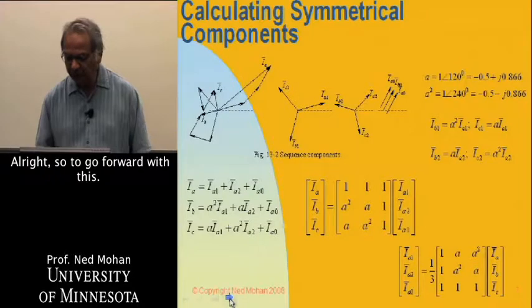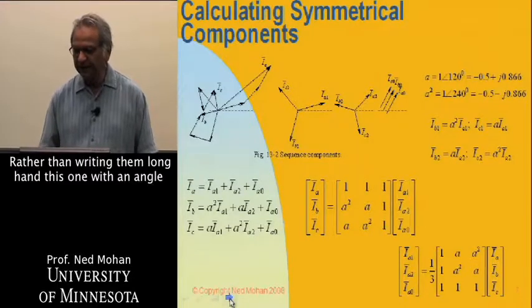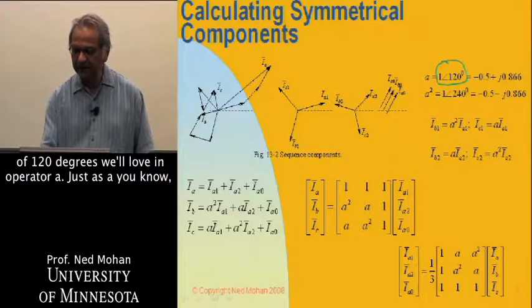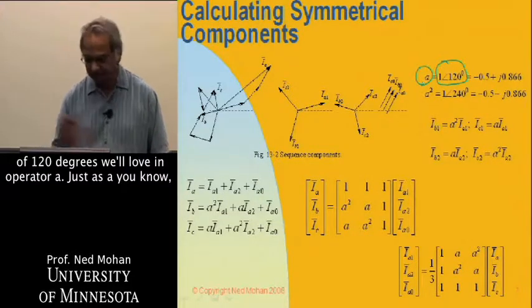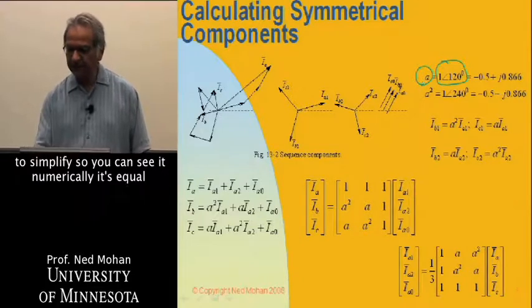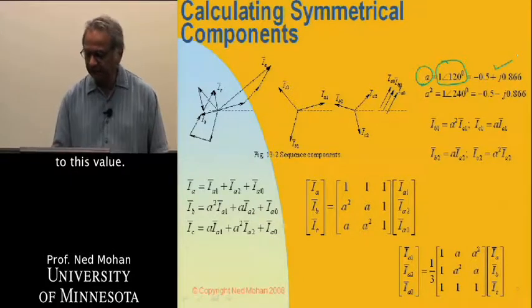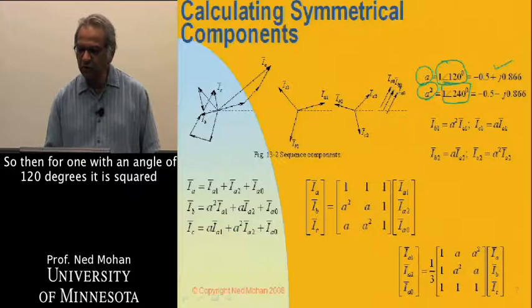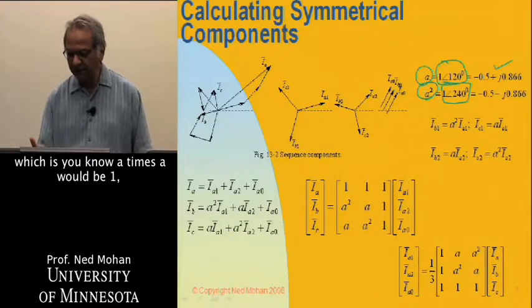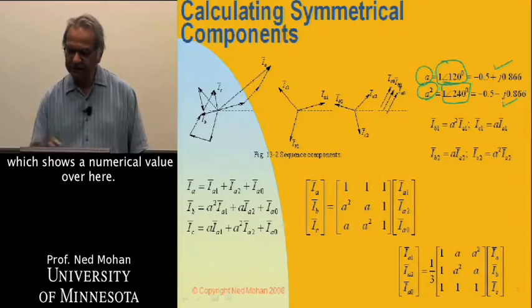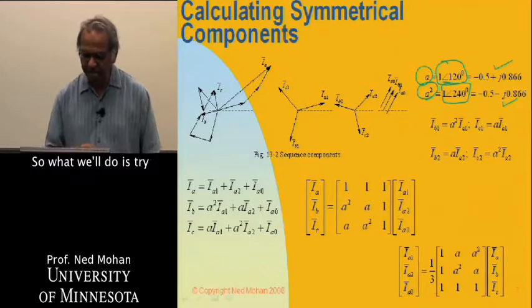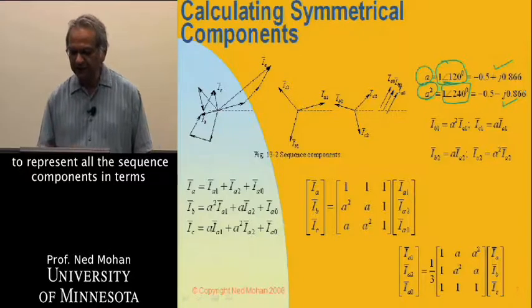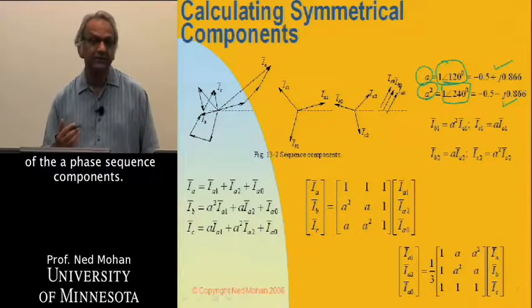To go forward with this, rather than writing them longhand, this one with an angle of 120 degrees, we'll use an operator A to simplify. You can see numerically, it's equal to this value. And then for one with an angle of 240 degrees, it's A squared, which is A times A would be one times angle of 240 degrees, which has a numerical value over here. What we will do is represent all the sequence components in terms of the A phase sequence components.